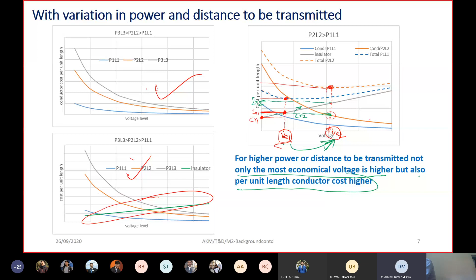In the last class, when I started, I told you that whenever I ask somebody why we go for higher voltage, they usually reply that if we go for the same power but higher voltage, the current will be lesser, meaning we can use a lower size conductor. Yes, of course that is correct. But for the most economical design, what happens is that if you are transmitting more power and going for higher voltage, they are using the higher size conductor as well. What does that mean? Let me repeat in simple language.